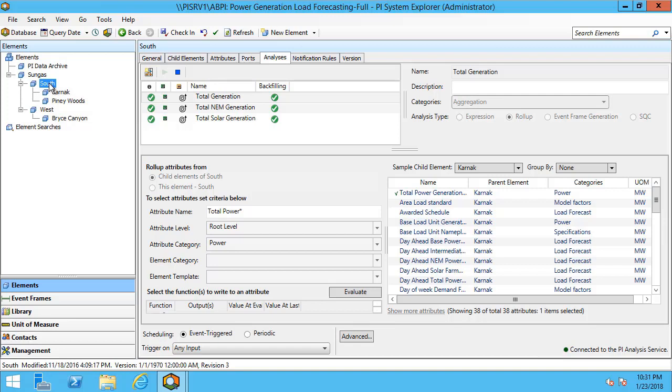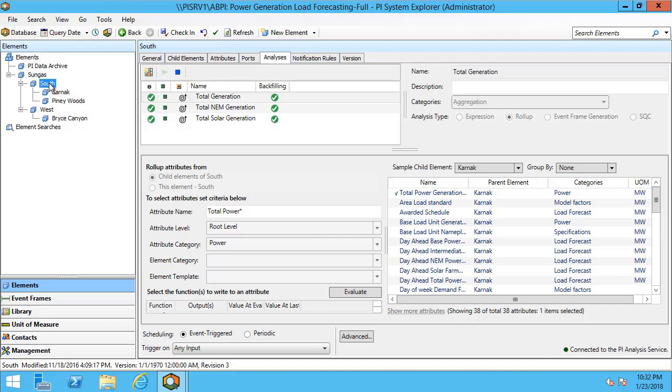Imagine that you had 10 plants in the South region. To get the total generation all you have to do is put in this one filter that matches on the same child attribute. Having similar child attributes is going to be easy because you'll likely be leveraging the use of templates. In that way you can easily filter on a child attribute value and quickly make many different calculations using the roll-up analysis. Let's take a look and make our own example for how we can use a roll-up analysis.